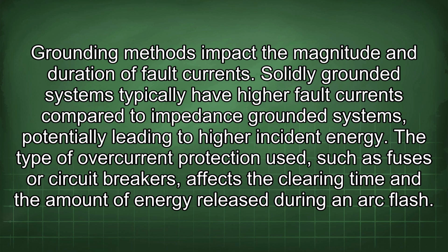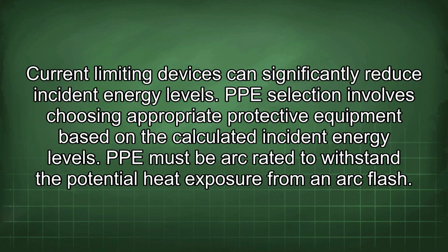The type of overcurrent protection used, such as fuses or circuit breakers, affects the clearing time and the amount of energy released during an arc flash. Current-limiting devices can significantly reduce incident energy levels.